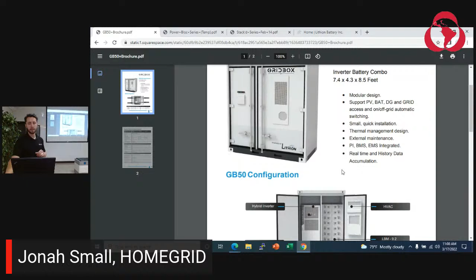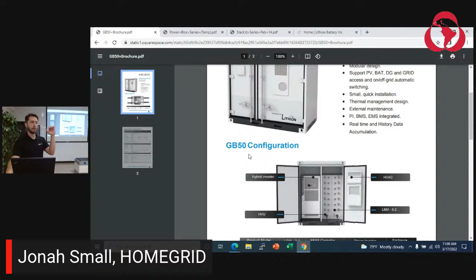Down at the bottom here we have the GridBox 50, which is basically an 8-foot shipping container. The names of our GridBox products indicate how much power they can output. On the smaller GridBox sizes, we have integrated hybrid inverters with our batteries and battery management system. This 8-foot container can go anywhere from 64 to 192 kilowatt hours in a single unit, with a hybrid inverter integrated. All our GridBox products output 480 volt 3-phase. This one, the GB50, can output 50 kilowatts continuous or charge at 50.